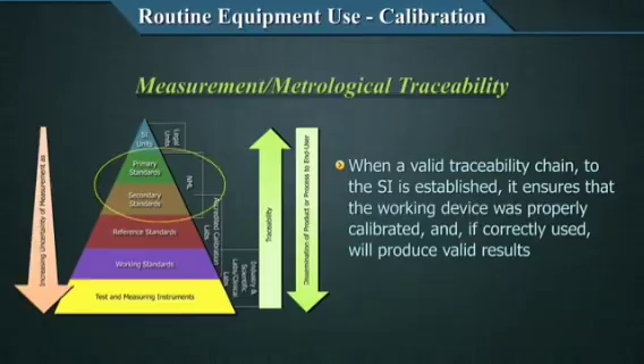When you look at the picture, therefore, it is important that an unbroken chain of comparisons is developed as far as practical, keeping in mind the degree of uncertainty of measurement that increases as the chain goes down. The degree of uncertainty must be mentioned on any calibrator or calibration certificate, depending on which the laboratory can decide the acceptability. This unbroken chain of comparisons is called the traceability. I hope that concept is clear.